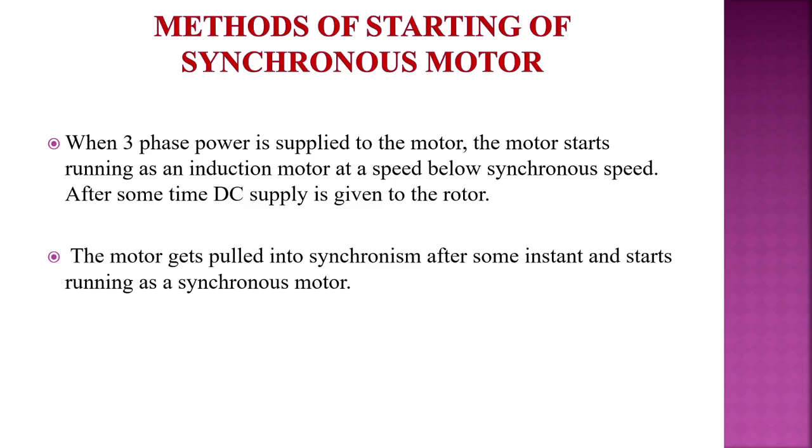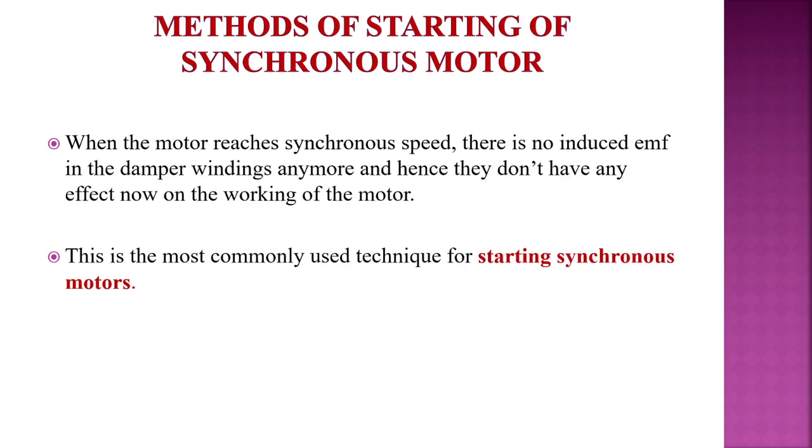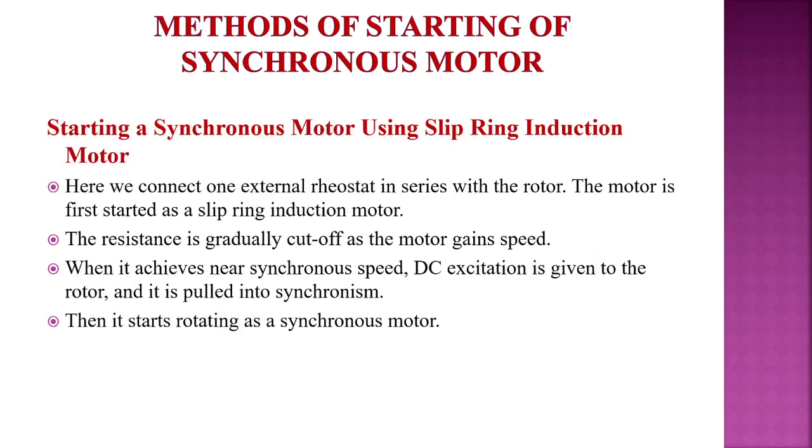So when three-phase power is supplied to the motor, the motor will start running as an induction motor at a speed below synchronous speed. After some time, DC supply is given to the rotor. So the motor will get pulled into synchronism after some instant and starts running as a synchronous motor. Whenever the motor reaches the synchronous speed, there will be no induced EMF in the damper windings anymore, and hence they don't have any effect on the working of the motor. This is the most commonly used technique for starting a synchronous motor. So we usually use damper windings to start the synchronous motor.